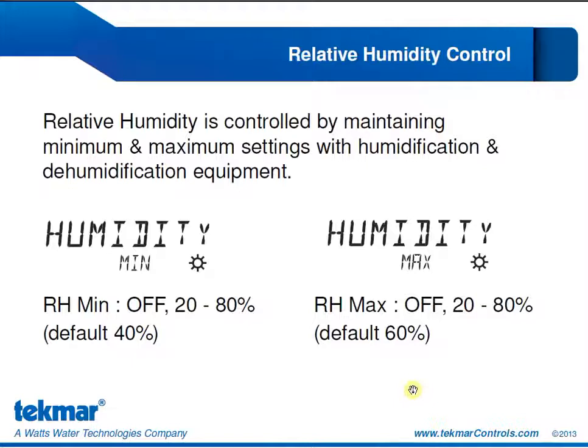Now that we know what relative humidity is, how do we control it? Well, we control it with the minimum and maximum humidity settings in the 557. We can configure a relative humidity minimum ranging from 20 to 80%, or we can turn it off if we don't have a humidifier. The default in the 557 is 40%. If we drop below the humidity minimum setting, we may notice dry skin, dry eyes, maybe difficulty breathing. Our kids might get nosebleeds. It's very uncomfortable. So we are going to enable the humidifier. The humidifier would be enabled whenever the humidity drops below that minimum setting, and it will turn off when we are 5% above the minimum setting.